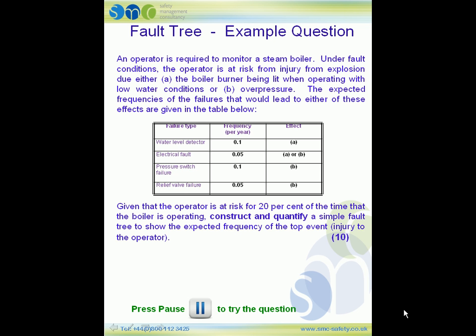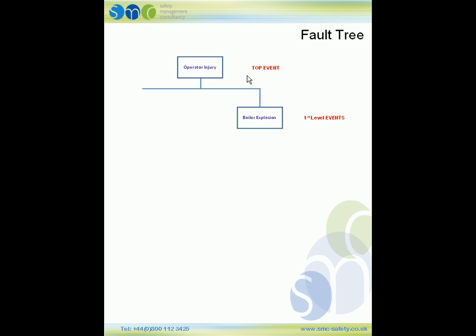Please press pause if you'd like to have a go at this question. Let's construct the fault tree. The first thing we need to do is identify the top event, which is the operator being injured. Now how can the operator be injured? We know it's due to the boiler explosion, but we also need the operator to be exposed. We need both of those conditions to happen — the operator exposed and the boiler explosion — and because of that, this is an AND gate.